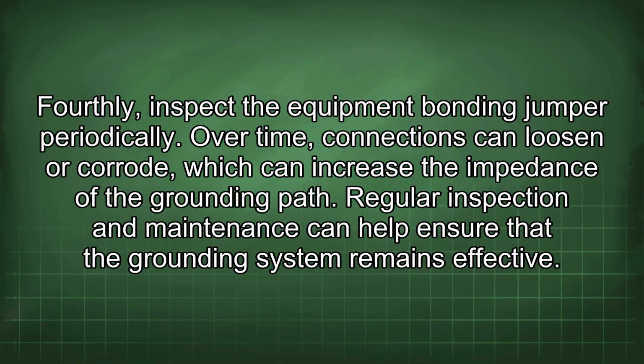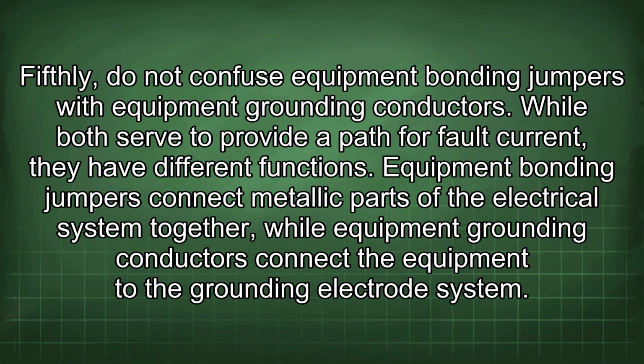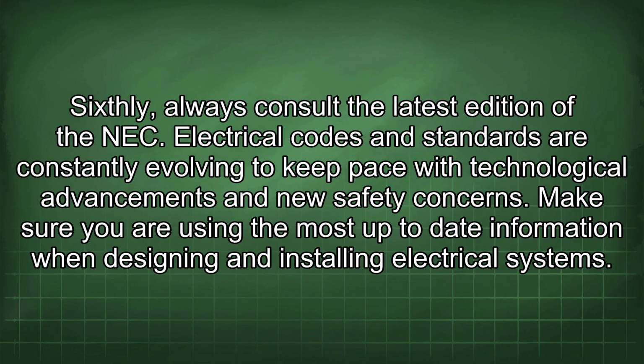Regular inspection and maintenance can help ensure that the grounding system remains effective. Fifthly, do not confuse equipment bonding jumpers with equipment grounding conductors. While both serve to provide a path for fault current, they have different functions. Equipment bonding jumpers connect metallic parts of the electrical system together, while equipment grounding conductors connect the equipment to the grounding electrode system. Sixthly, always consult the latest edition of the NEC.